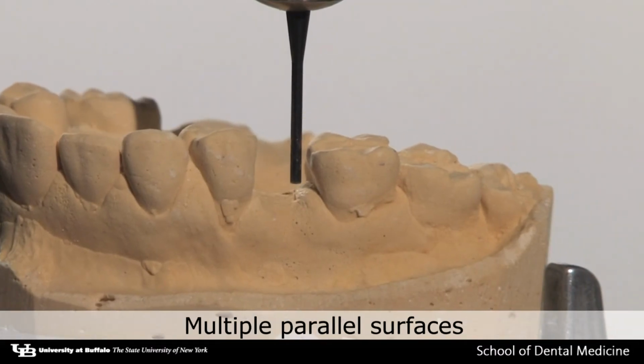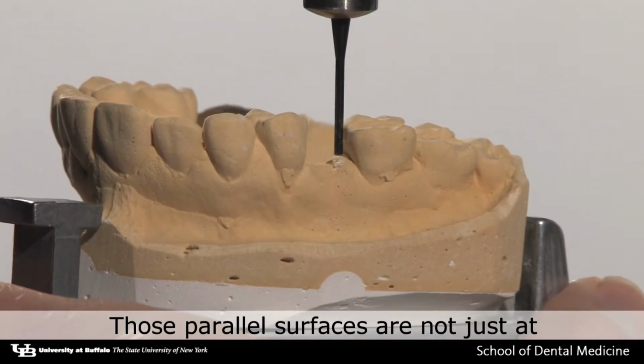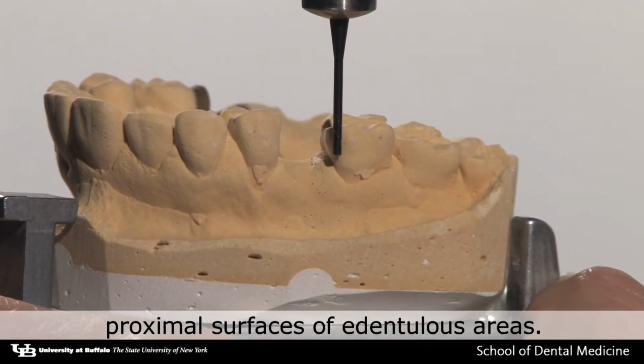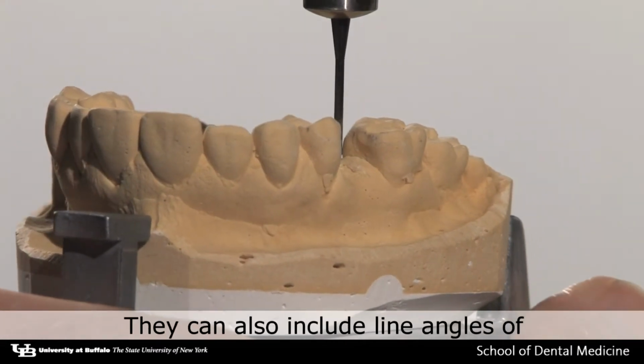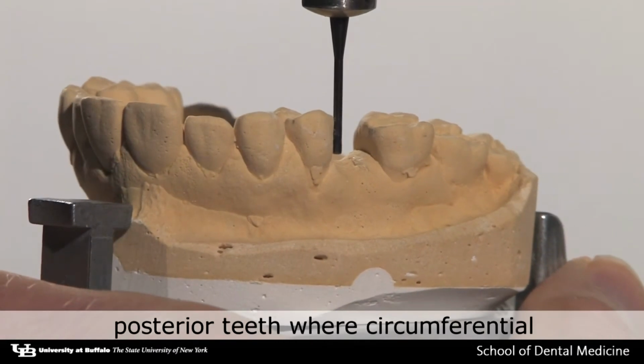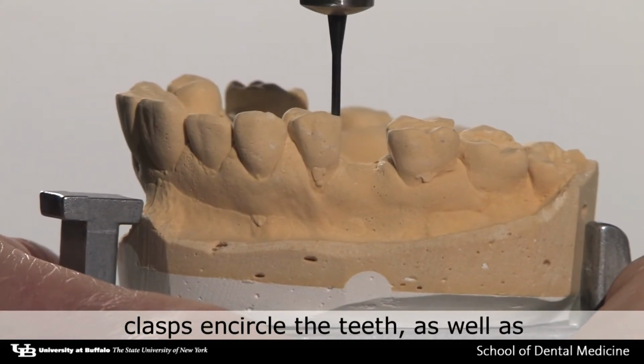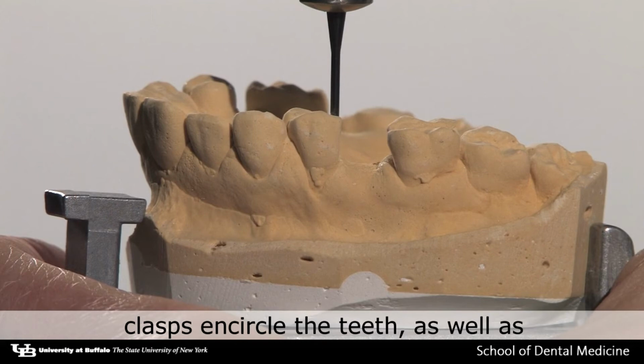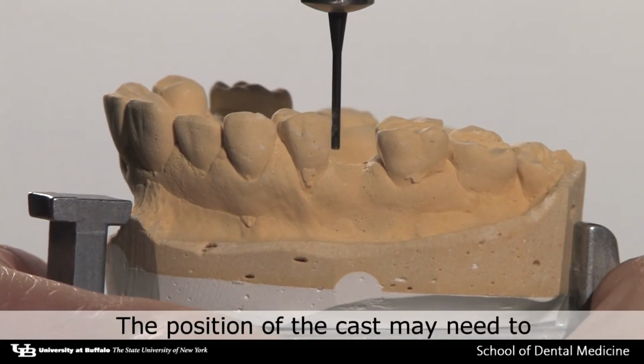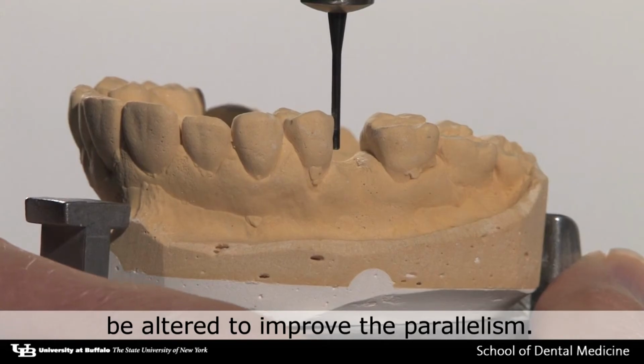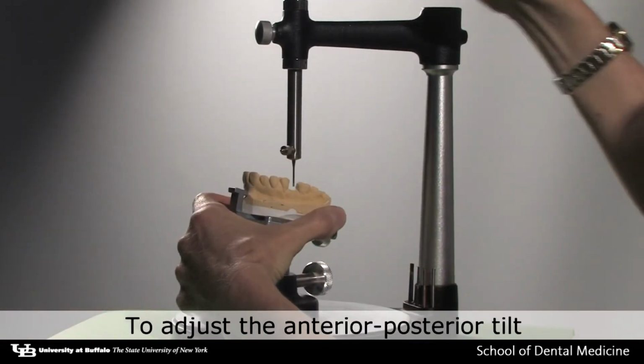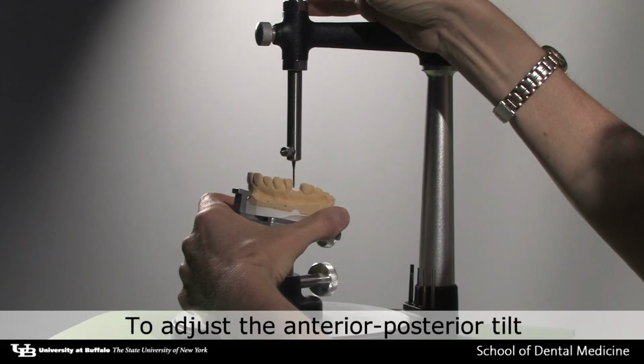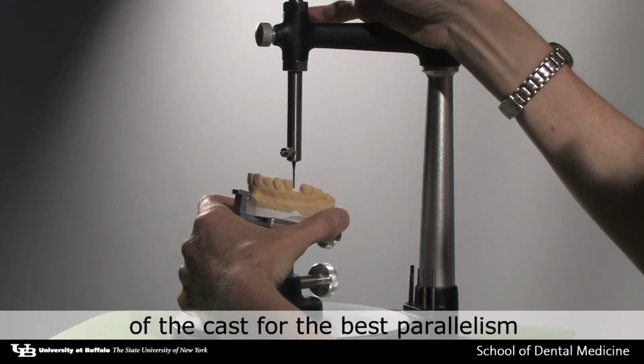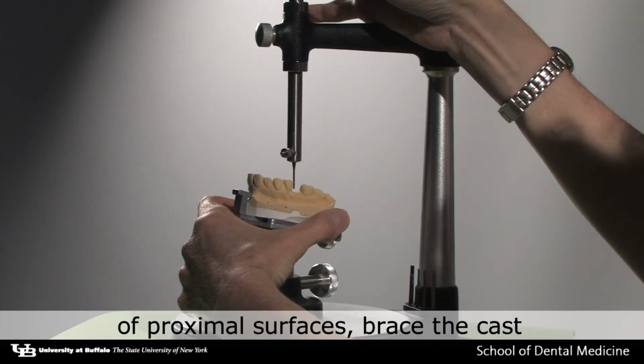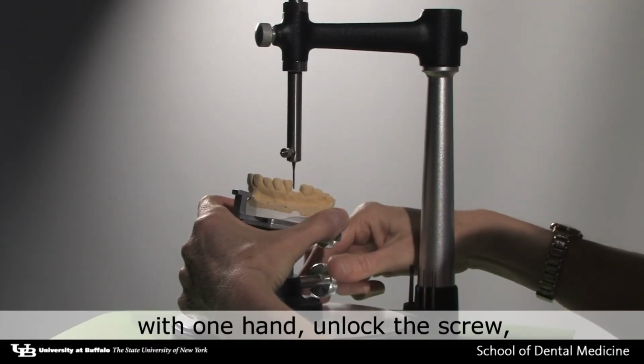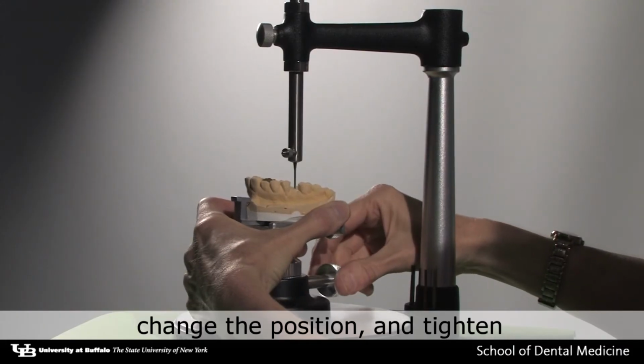Multiple parallel surfaces produce retention. Those parallel surfaces are not just at proximal surfaces of edentulous areas. They can also include line angles of posterior teeth where circumferential clasps encircle the teeth, as well as lingual surfaces. The position of the cast may need to be altered to improve the parallelism. To adjust the anterior-posterior tilt of the cast for the best parallelism of proximal surfaces, brace the cast with one hand, unlock the screw, change the position, and tighten the screw.